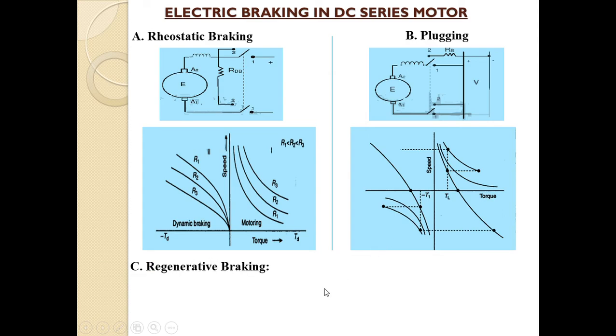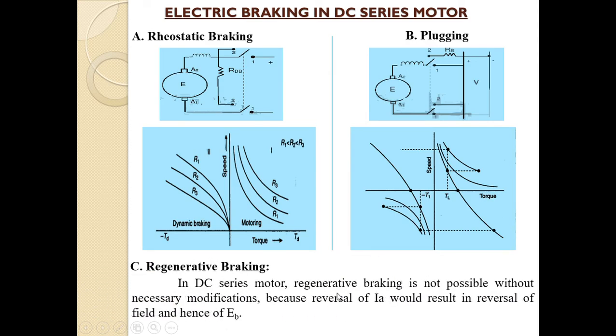The last method is regenerative braking for the DC series motor. Regenerative braking is not possible in a DC series motor without necessary modifications, because reversal of armature current would result in reversal of the field and hence of the back EMF. Due to the series connection of the armature coil and field coil, regenerative braking is not straightforward. Thank you all.